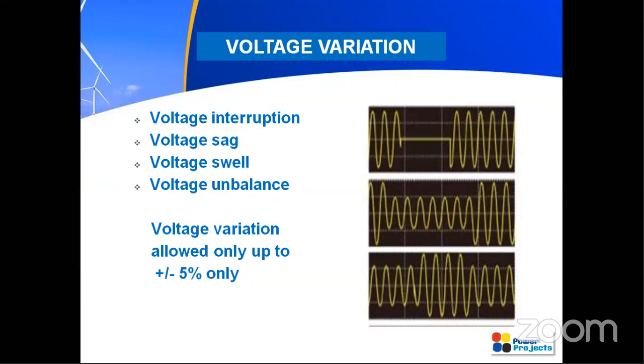Coming to the voltage variation, you can see in this graph, this is a voltage interruption, this is a voltage sag, and this is a voltage swell. All these are power quality issues, and they may be due to faults or whatever problems in the grid. These power quality issues are often common in the grid. So during that time, what should be the voltage variation allowed? That is the main thing I'm stressing here. The voltage variation in your grid connected wind farms should be limited to plus or minus 5% only. This is very, very important. I will deal with this voltage variation along with the short circuit contribution in detail so that you can understand very clearly.